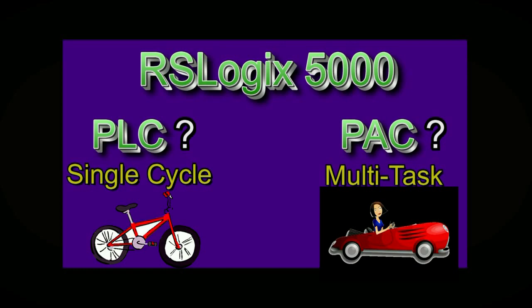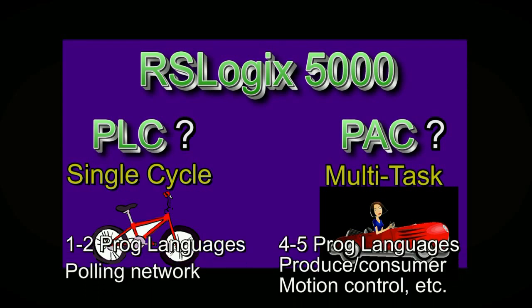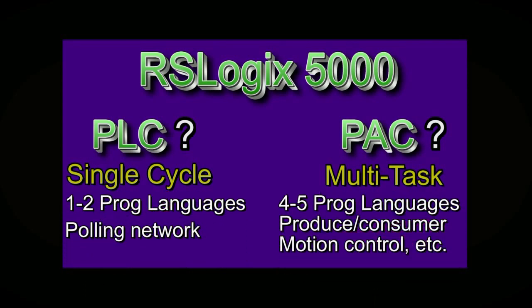A PAC can take the place of multiple PLCs. A PLC typically has 1-2 programming languages, a PAC 4-5. A PLC is restricted to polling a network and backplane in between scan cycles, whereas with a PAC, every module is a device on the Ethernet network.